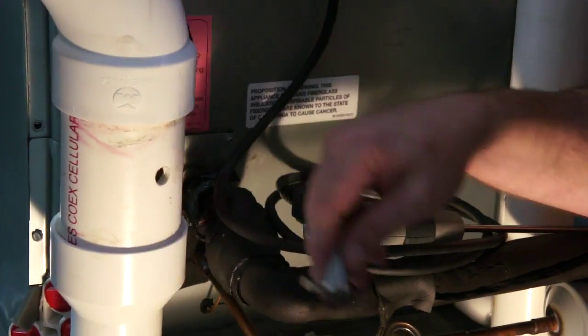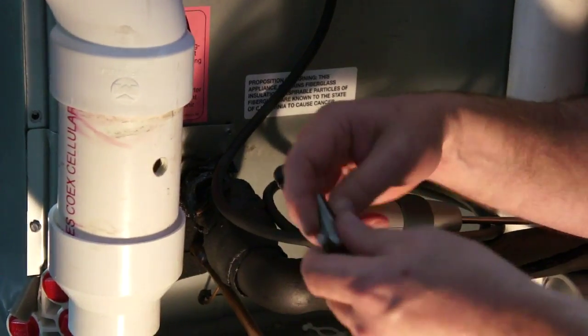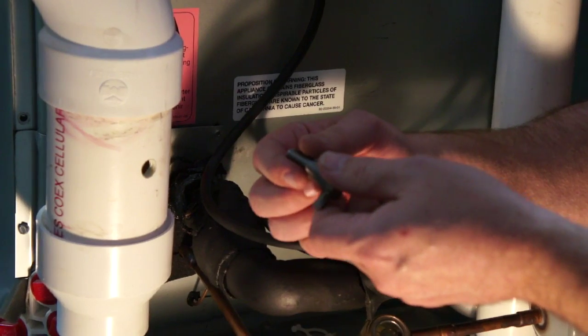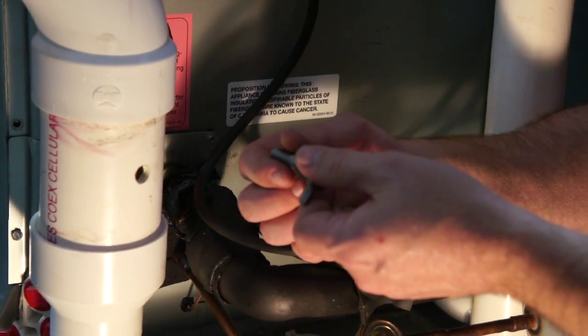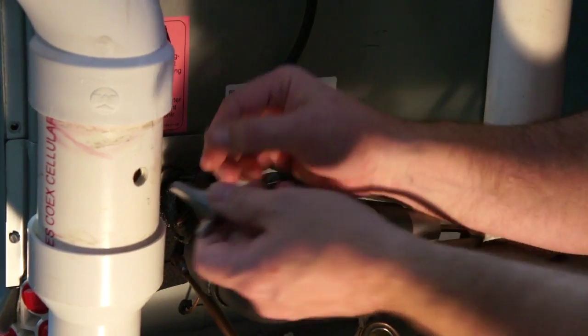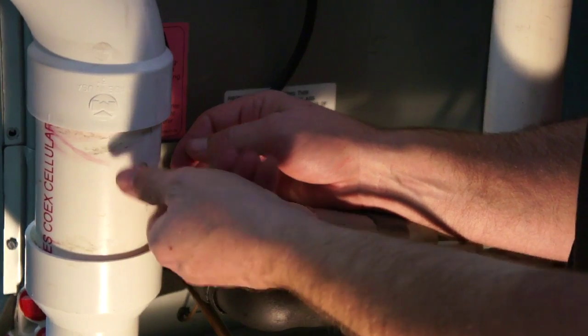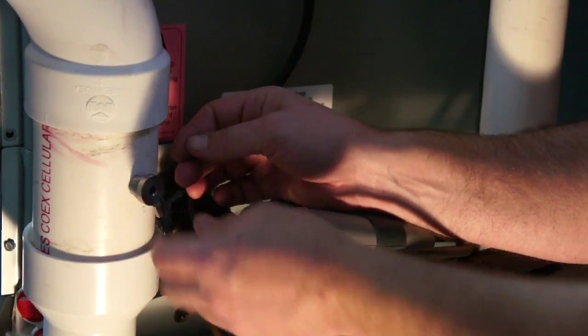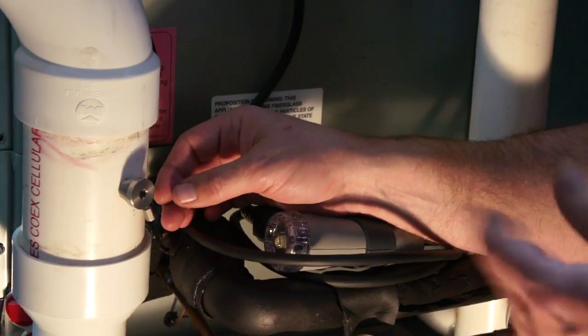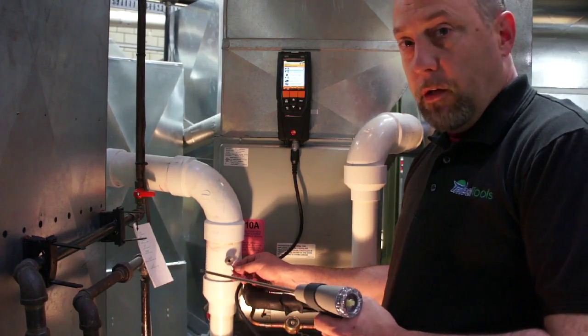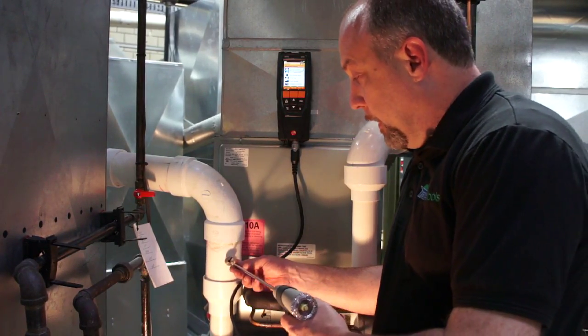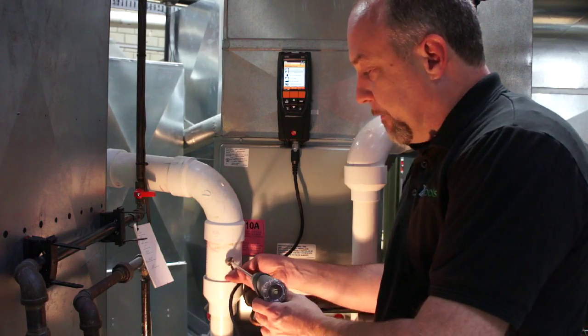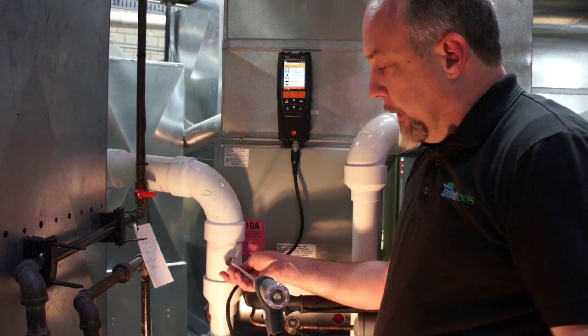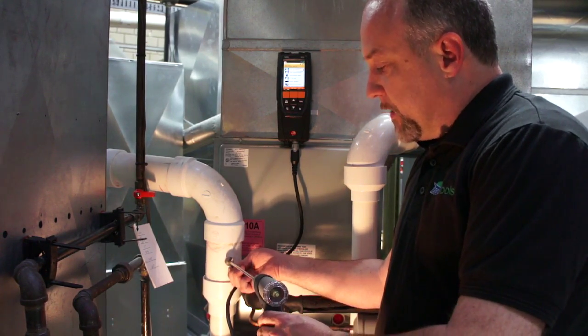I like using the Allen screw simply because it's a little bit more tamper-proof than some other types of connections we could use, like a screw thread. Now all I've got to do is take my cone assembly, which is tapered and threaded into the flue pipe, and I'm all set to do my combustion test. Alright, so now I've got the cone assembly in here. All we've got to do is slide the probe shaft in, touch the back of the pipe, pull it about halfway out, and then tighten up the set screw here so the probe assembly is locked in for testing.